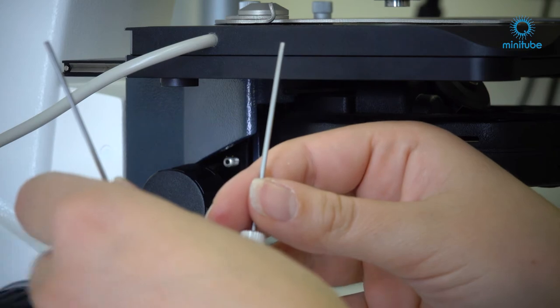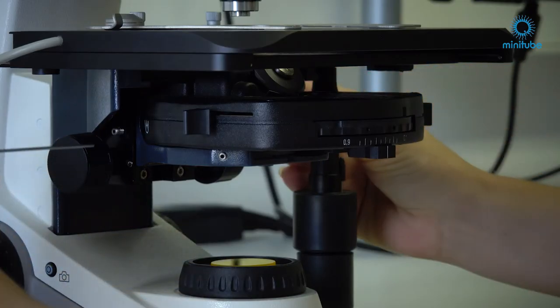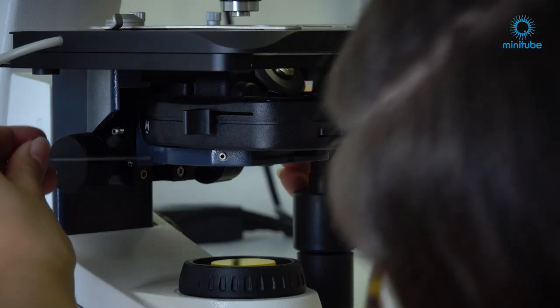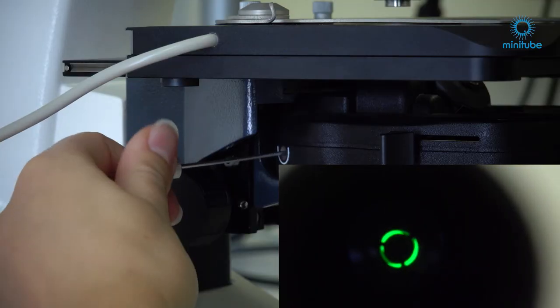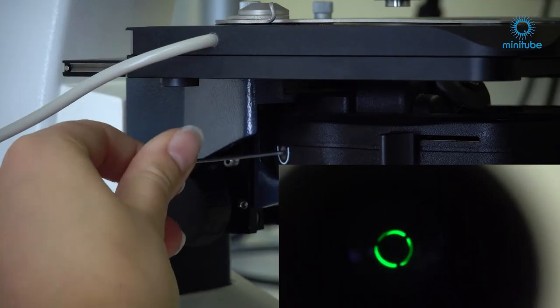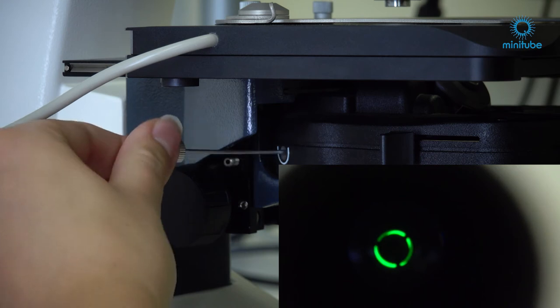Use the two screws on both back sides of the condenser. Now you have to achieve a full overlap between the lighter annular diaphragm in the condenser and the darker phase ring of the objective.